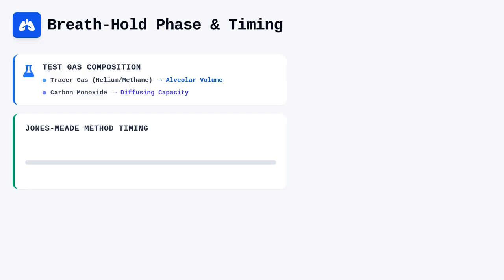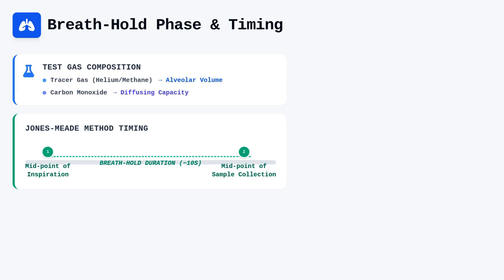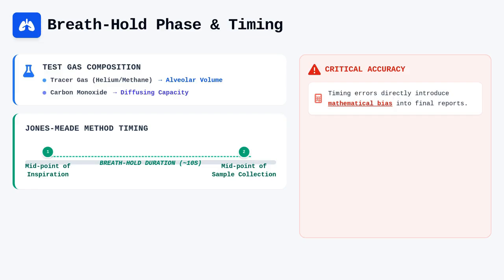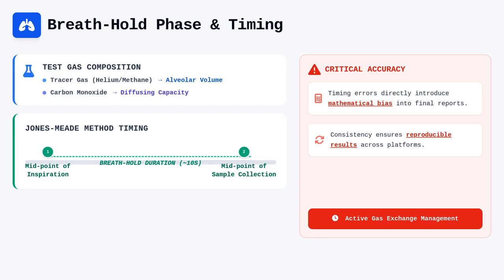When measuring the breath hold timing, we generally apply the Jones-Meade method, which calculates the start of the breath hold at the midpoint of inspiration and the end at the midpoint of the actual sample collection. This timing configuration accounts for the time during which gas exchange is actively occurring throughout the maneuver. Proper isolation of these intervals is critical because any error in timing duration will directly introduce mathematical bias into your final diffusing capacity report. Consistency in these time-based intervals ensures that your results remain reproducible across different sessions and equipment platforms.